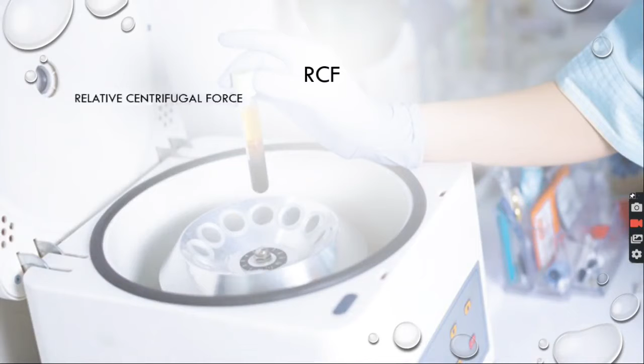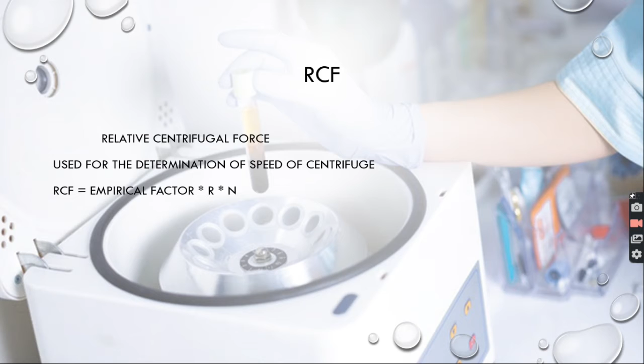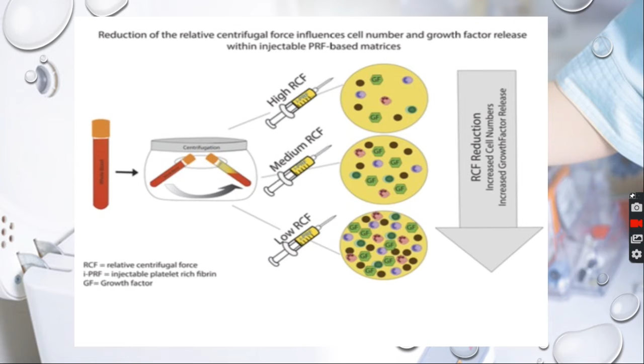What is RCF? RCF is relative centrifugal force. It is used for the determination of the speed of the centrifuge. What is the formula of RCF? RCF is equal to empirical factor times R times N, where R is the horizontal distance or radius, and N is the speed of rotation in RPM. This is the diagram showing that reduction of relative centrifugal force influences cell number and growth factor released with injectable PRF based matrices. You can see the results when we provide high RCF, medium RCF and low RCF.